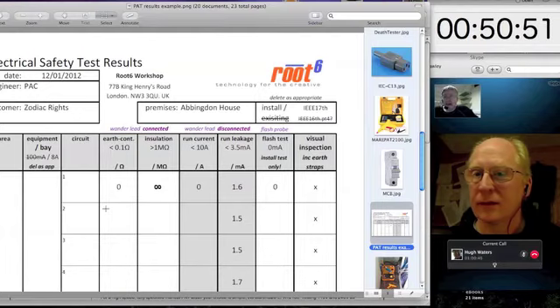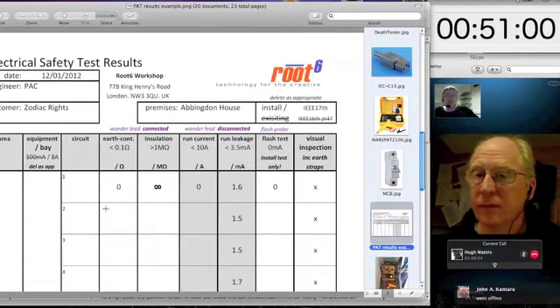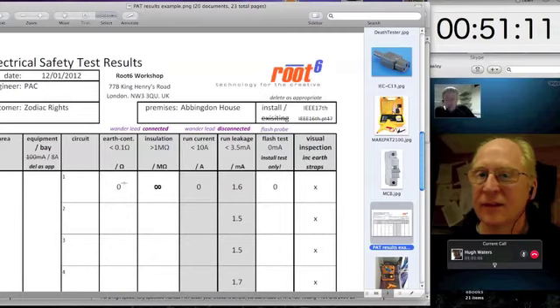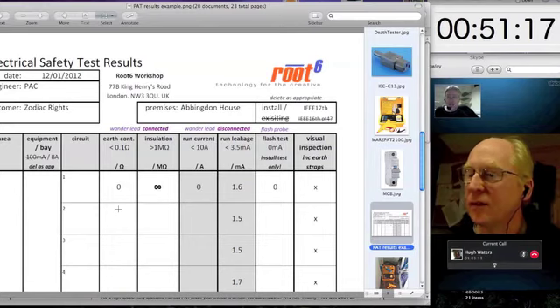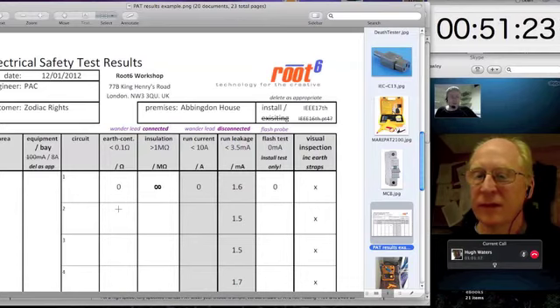That test is typically carried out at only 6 volts, but with many amps. So our machine we typically test at 8 amps, and if there's any fault within the earth path, any just kind of whiskers of conductivity hanging on, that will burn them out, and the test will fail, and you get a readout of the impedance on the machine, but it's an impedance that's been tested at a very high current, and it's something you can't do with a digital multimeter. You can't do that with your multimeter. I mean, you can make the measurement, but you can't be assured that it's meaningful from an earth safety point of view.